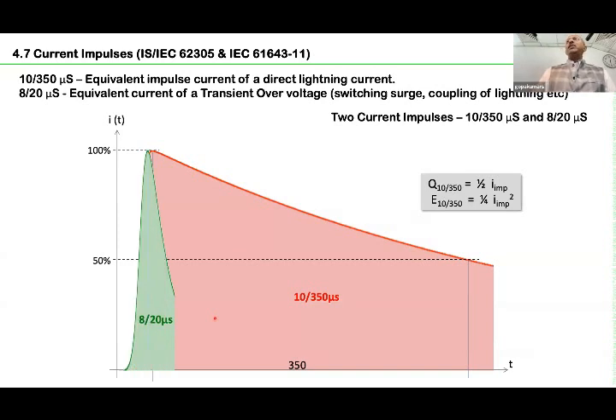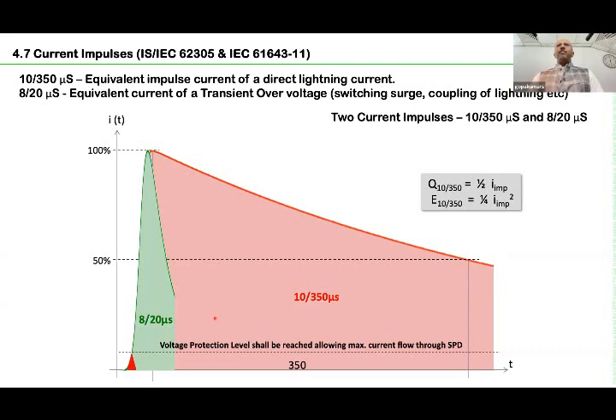The next wave shape is called 8/20 microseconds, which is the equivalent energy of a switching surge. Once we operate some electrical apparatus, transient over voltages are created, and the energy is very low. Those energies are termed 8/20 microseconds. What is the purpose of this terming? Everybody should manufacture a product according to a certain standard, so these are the standardized current wave shapes. 10/350 is direct lightning, 8/20 is a switching surge or a capacitive or inductively coupled surge.